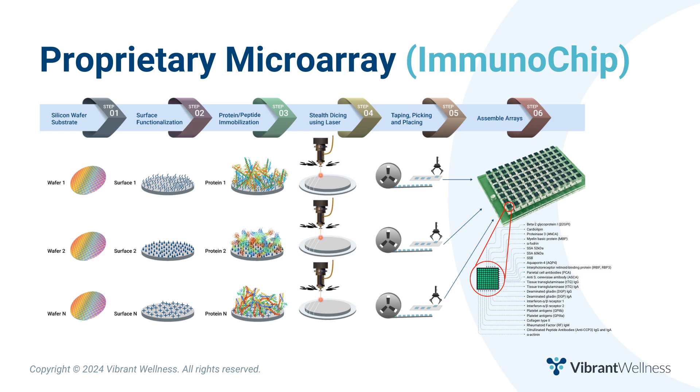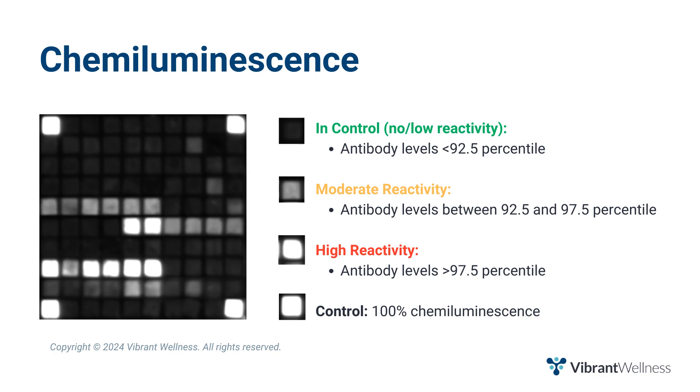Vibrant measures antibody levels using a proprietary microarray plus chemiluminescence. The microarray works similar to ELISA methodology. However, instead of one antigen per well, we can measure up to 96 antigens per well. This is possible because we attach antigens to silicon wafers, then dice the wafers into tiny microchips, then arrange the microchips — one for each antigen — in a 4x4 or 10x10 grid atop one pillar on a 96 or 24-pillar plate. 10x10 equals 100 minus 4 controls equals 96 antigens tested.